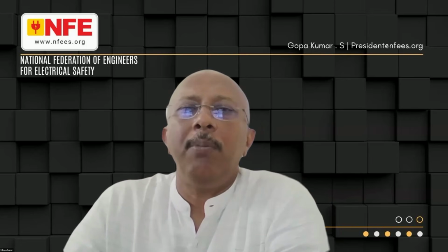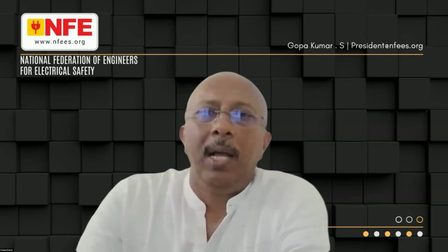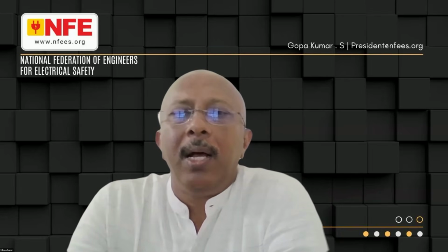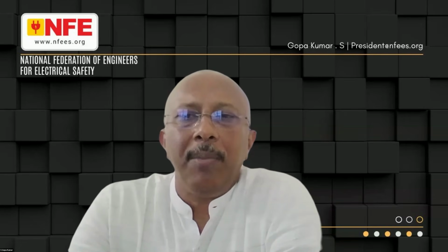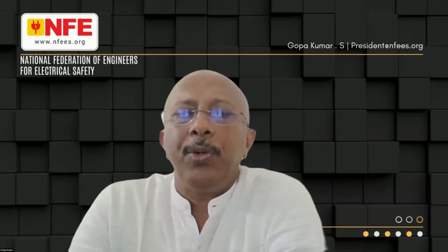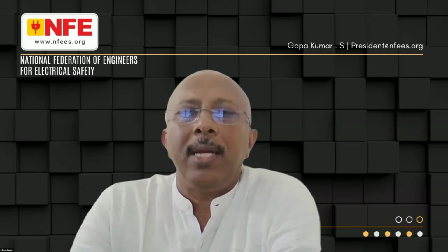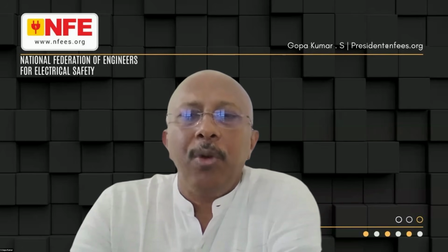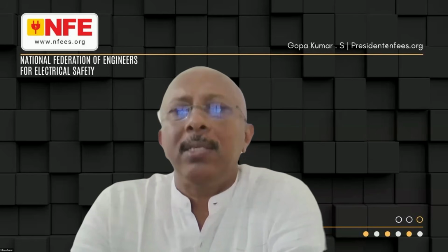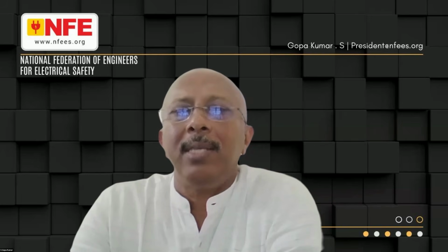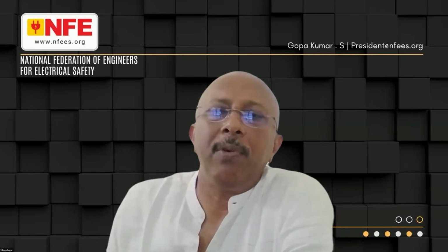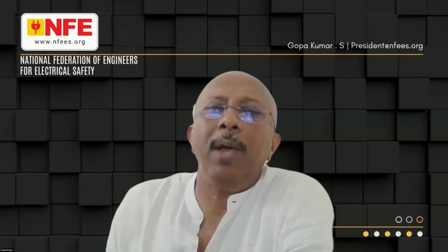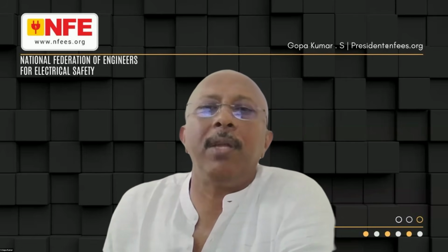So the next question. What measures can be undertaken to assess and evaluate a hospital that has already been constructed and operational for a significant period of time? In an existing hospital, you have to assess the requirement. Again, the process is same. The type of biomedical equipment which you are using, the areas where you are using, the communication which is going on between the equipment, the type of oxygen content, all these measures which I explained in the previous slides, you need to assess. You need to find out the type of sources, type of changeover between the sources, type of backup system which you have, type of medical IT system which you have, and you have to assess all these things and decide on what kind of thing you are going to use.